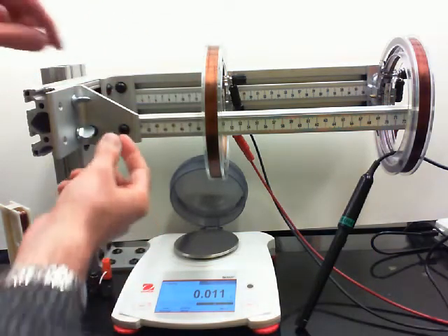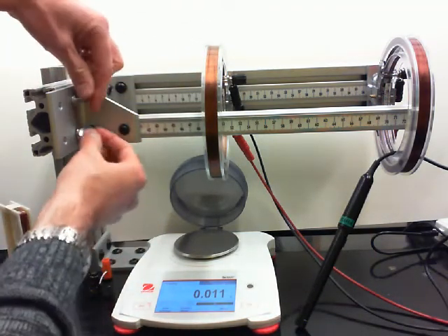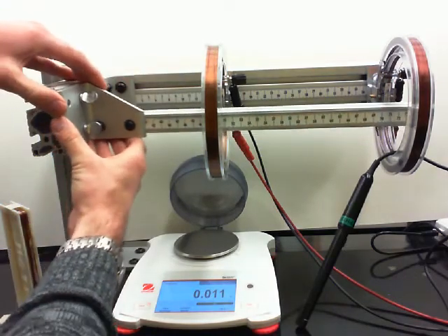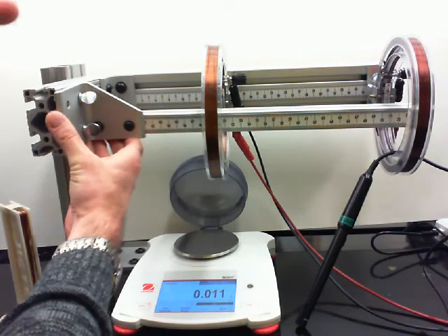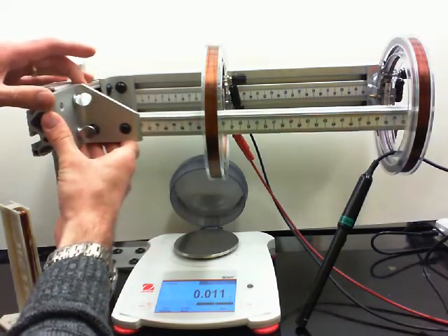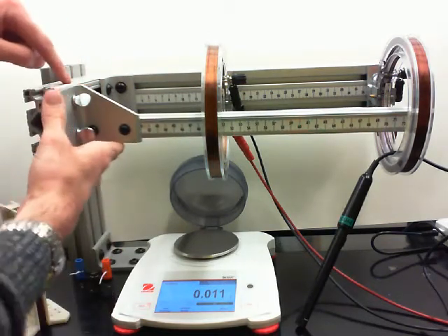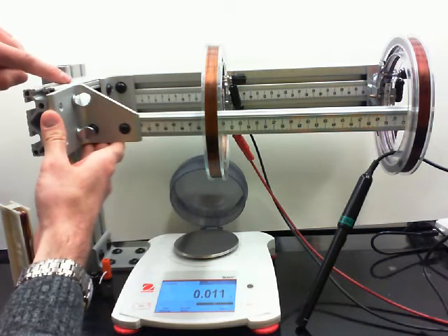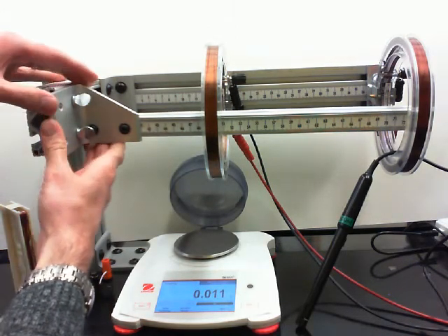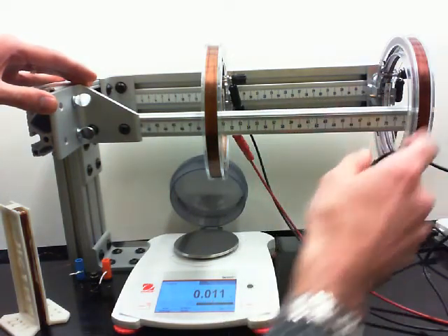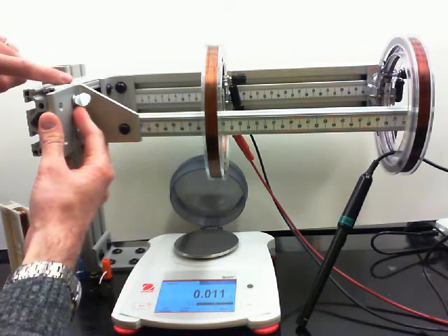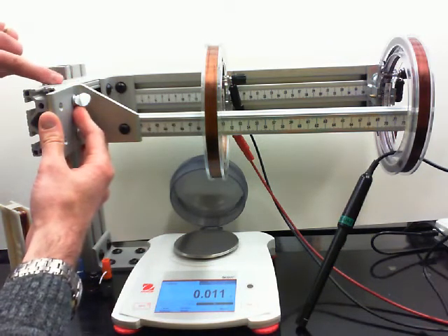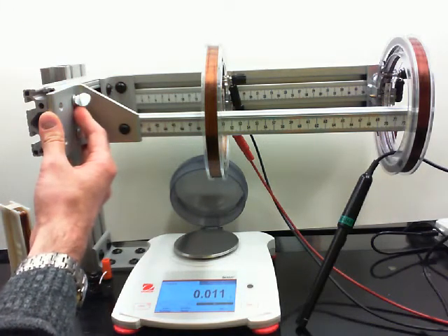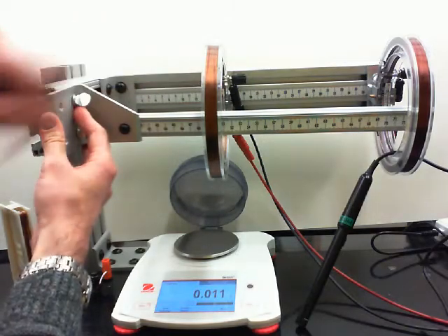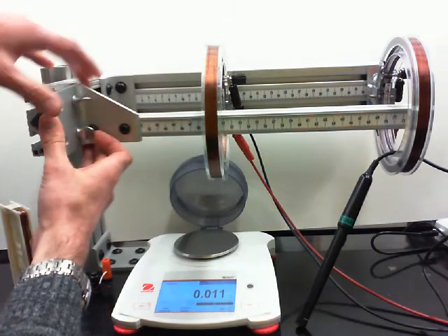To change where this guide is located with respect to the coil, we can adjust these two thumb screws located right here. These screws easily get loosened, and now this guide can slide back and forth. From your point of view, it's sliding in and out. You'll notice that there's an indication on the top here which shows when the guide is set up so that it's perfectly centered on the axis of the coils. When the little arrow on this slide matches up with the mark on here, which is right near the 80 centimeters mark, that means that the magnetic probe guide is coaxial with these coils. And that's the central first position that you're going to be recording.